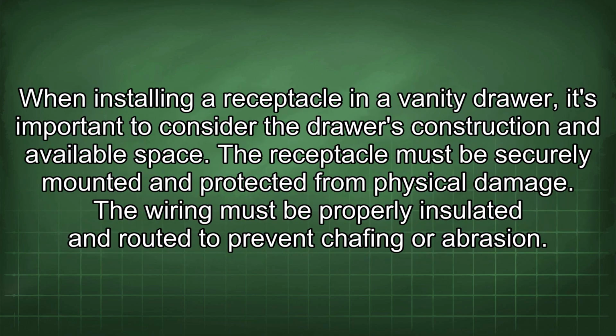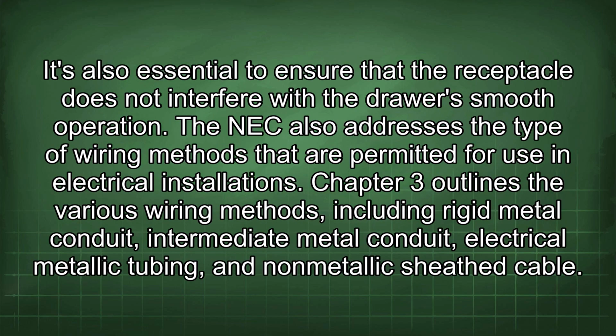When installing a receptacle in a vanity drawer, it's important to consider the drawer's construction and available space. The receptacle must be securely mounted and protected from physical damage. The wiring must be properly insulated and routed to prevent chafing or abrasion. It's also essential to ensure that the receptacle does not interfere with the drawer's smooth operation.